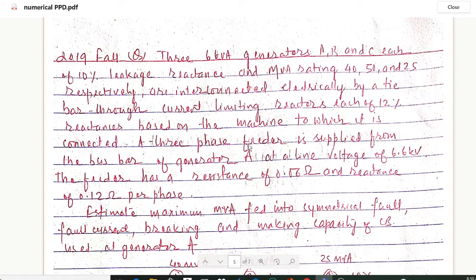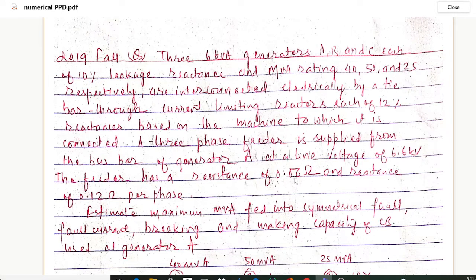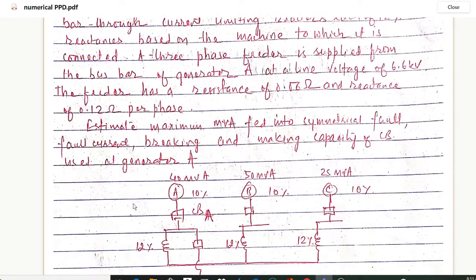A three-phase feeder is supplied from the busbar of generator A at a line voltage of 6.6 kV. The feeder has a resistance of 0.06 ohm and reactance of 0.12 ohm per phase. We have to estimate the maximum MVA fed into a symmetrical fault, the fault current, and the breaking and making capacity of the circuit breaker used at generator A.